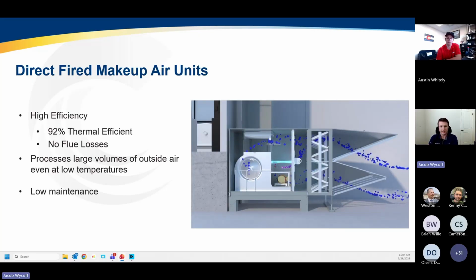They're also extremely advantageous for these applications because they're able to process very large volumes of outside air. The M Series makeup air unit from Cambridge Air Solutions, available all the way up to 75,000 CFM in a single package. And they're able to give you the temperature rise that you need even on the coldest day of the year. That's something that your other technologies like indirect fired equipment and especially electric equipment can tend to struggle with, being able to provide the needed heat on the coldest day of the year.